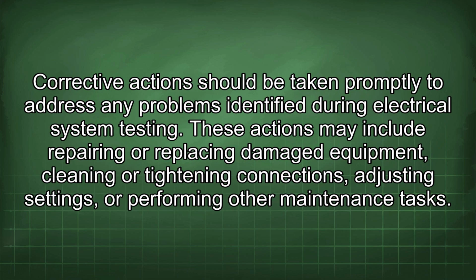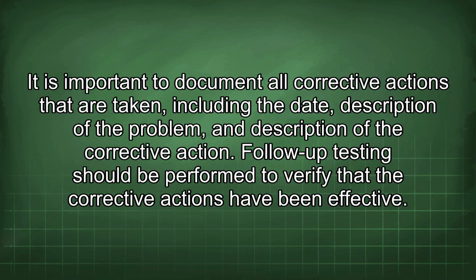Corrective action should be taken promptly to address any problems identified during electrical system testing. These actions may include repairing or replacing damaged equipment, cleaning or tightening connections, adjusting settings, or performing other maintenance tasks. It is important to document all corrective actions that are taken, including the date, description of the problem, and description of the corrective action. Follow-up testing should be performed to verify that the corrective actions have been effective.